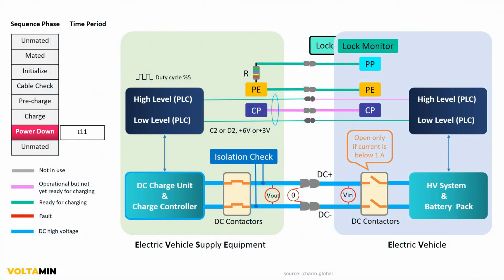At T11, after ensuring that the current is below 1 A at the disconnecting point on the EV side, the EV opens its disconnection device. The EV then sends a message to the DC supply to disable its power output.